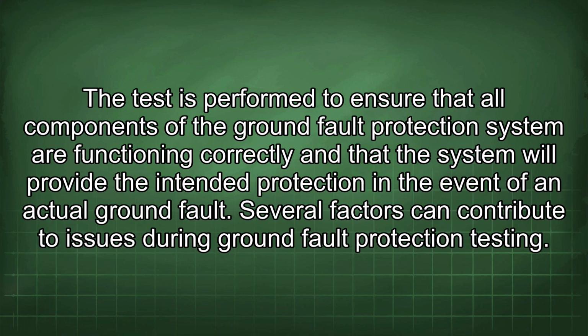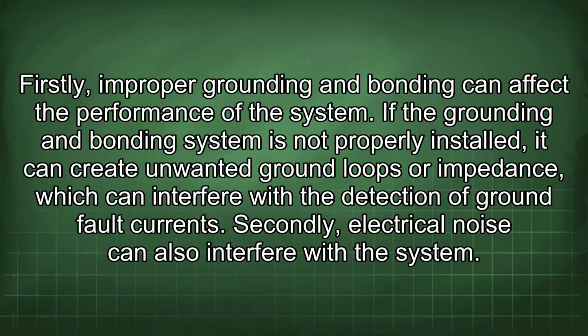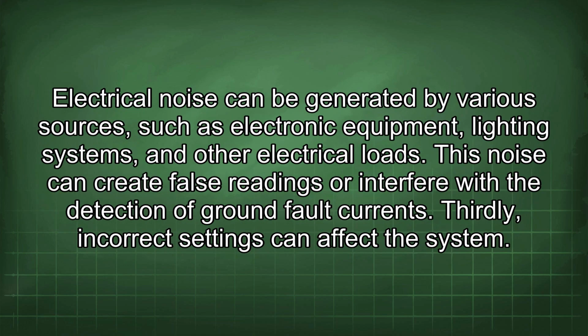Several factors can contribute to issues during ground fault protection testing. Firstly, improper grounding and bonding can affect the performance of the system. If the grounding and bonding system is not properly installed, it can create unwanted ground loops or impedance, which can interfere with the detection of ground fault currents. Secondly, electrical noise can also interfere with the system. Electrical noise can be generated by various sources, such as electronic equipment, lighting systems, and other electrical loads. This noise can create false readings or interfere with the detection of ground fault currents.